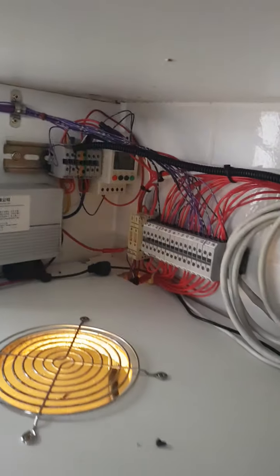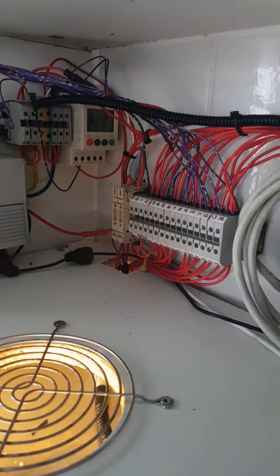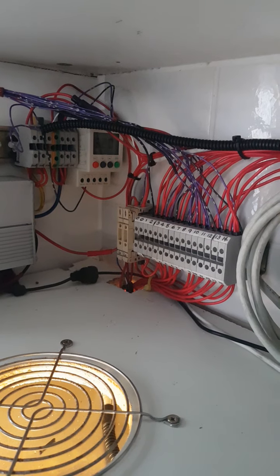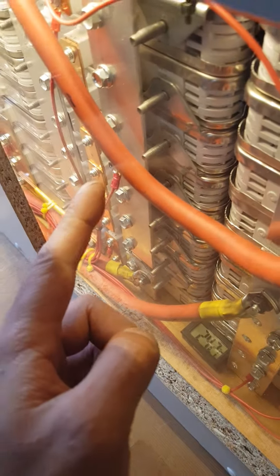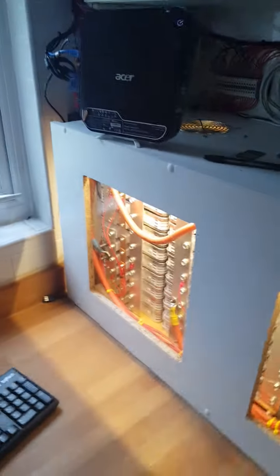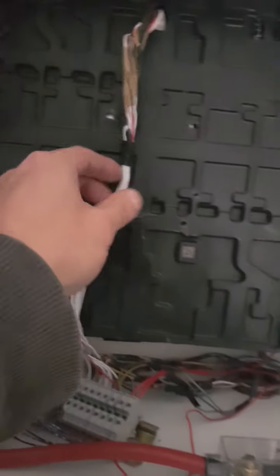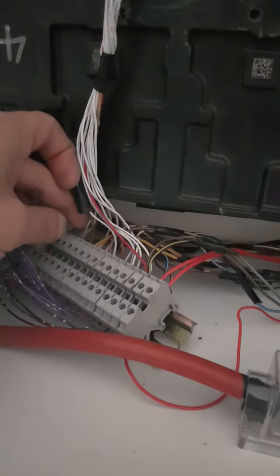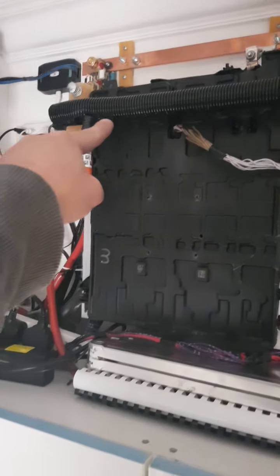So, similar thing again, that's all your BMS wiring - that's all the ones from the top down into the same terminals and all the ones at the bottom. So what we're doing is taking each BMS wire, the little ones, and connecting them up to the BMS wiring up here, and then each one goes together through the terminal block. So you can see down there, say cell 1 up here, and then it'll be connected cell 1, cell 1, cell 1, and then down there also cell 1. So they'll all be joined together.